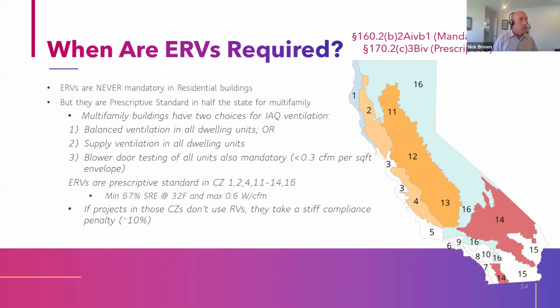These are going to have even more benefit in your areas, Pam. So multifamily buildings today, and this is a big change for 2025, have two choices for IAQ ventilation: balanced or supply. What did I not mention? Exhaust. Exhaust is forbidden now in multifamily. This was a huge change for 2025. Blower door testing of all units is mandatory to confirm these have been built tight, so the ventilation systems aren't just swapping air from unit to unit, but bringing in actual fresh air.